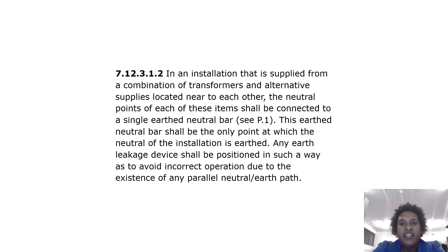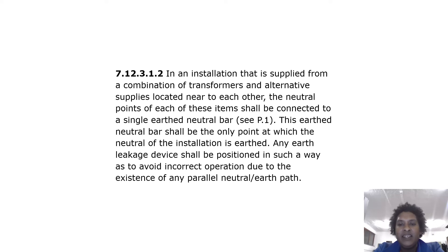In an installation supplied from a combination of transformers and alternative supplies located near to each other, the neutral points of each shall be connected to a single earth neutral bar. This earth neutral bar shall be the only point at which the neutral of the installation is earthed. Any earth leakage device shall be positioned to avoid incorrect operation due to the existence of any parallel neutral-earth path.